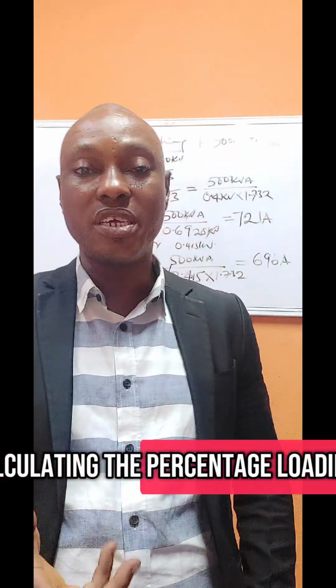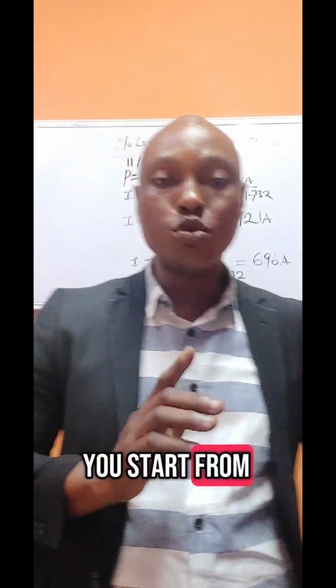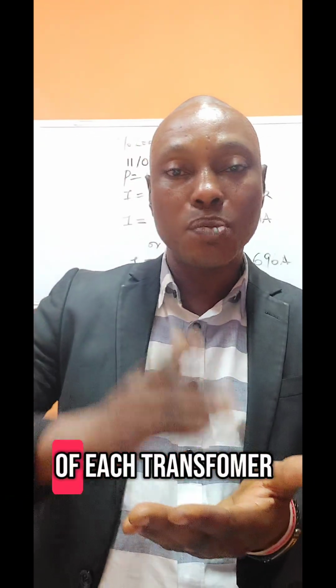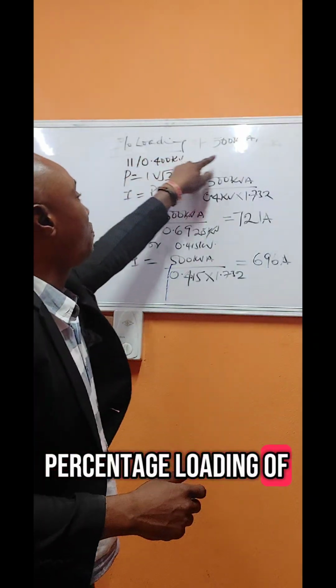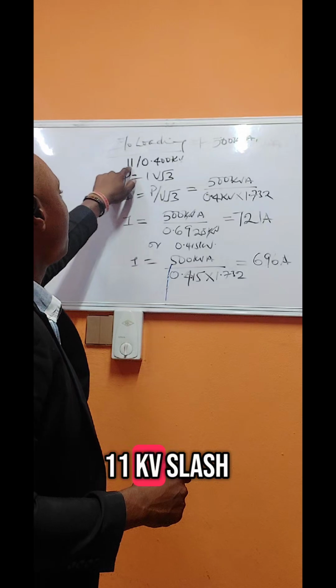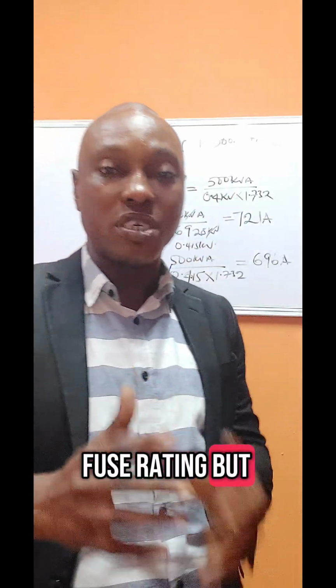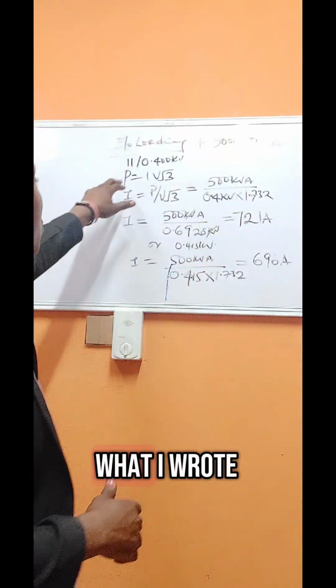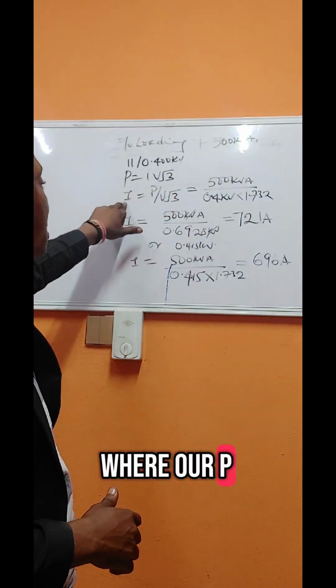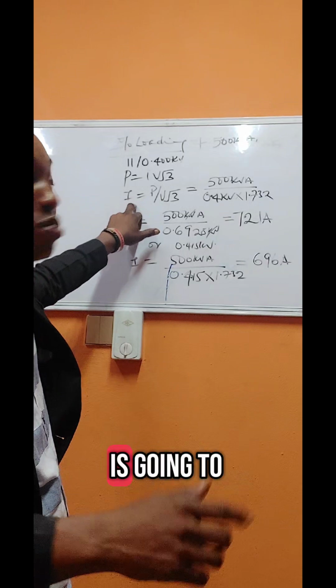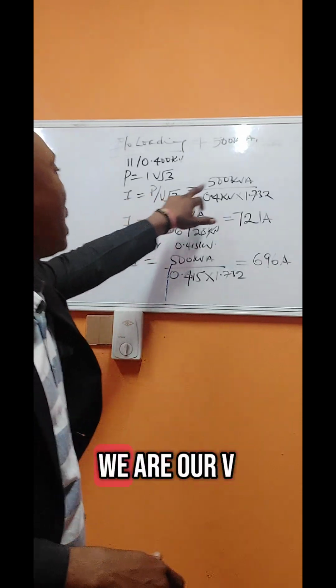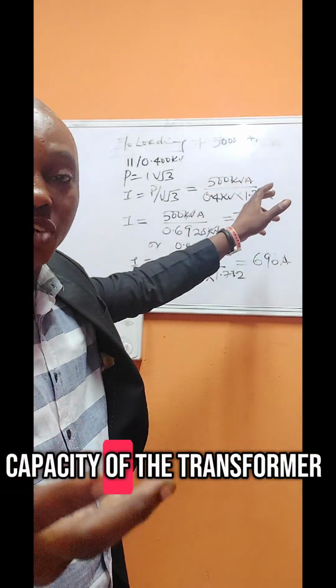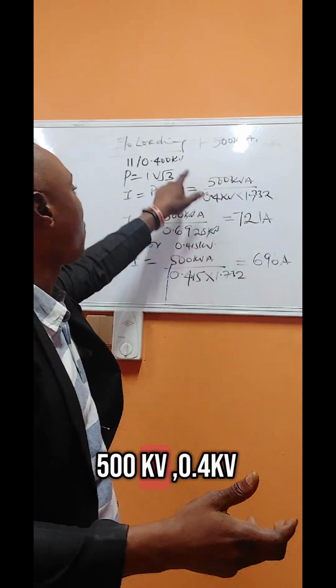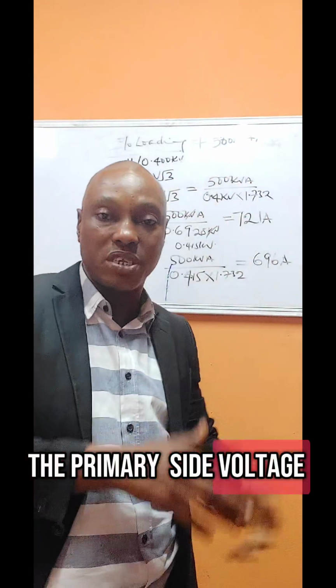So let's go to our calculation part. Calculating the percentage loading of the transformer, you start from knowing the load per phase of every transformer. Now look at our question: percentage loading of a 500 kVA, 11 kV/0.41 kV transformer. We will still use the same formula we use for our fuse rating, but this time it's on the secondary side. Now you see what I wrote: P = √3 × V × I, so I is going to be P over √3 × V, where P is the capacity of the transformer, 500 kVA, and V is 0.4 kV, the secondary side voltage of that transformer.